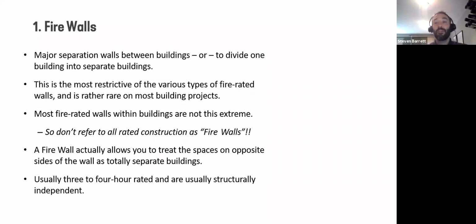So the few of you that said firewalls on the poll question, pay attention. It's not just semantics. It really is important to differentiate these different types. A firewall is a special type of construction. It's actually pretty rare. It's used to divide a building into separate buildings. It's the most restrictive type of fire-rated partition you can have, or fire-rated assembly is a better word. And most of the time, they're not this extreme. So try to avoid using that term firewall. And I'll admit some architects will use it incorrectly, but if you do have a firewall, it allows you to separate the 2 buildings and treat them as separate buildings.